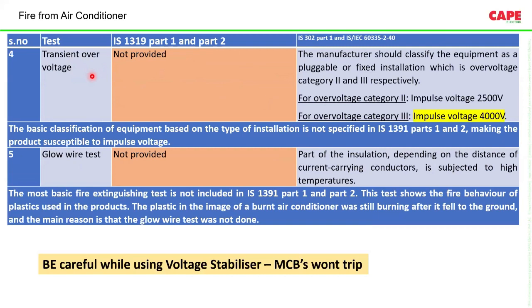Every electrical appliance which is used in an electrical installation, the equipment manufacturer is supposed to categorize as per overvoltage category. Air conditioners are actually part of the fixed electrical installation. They are not portable appliances. They are fixed electrical installation. Generally, they have to come under overvoltage category 3.